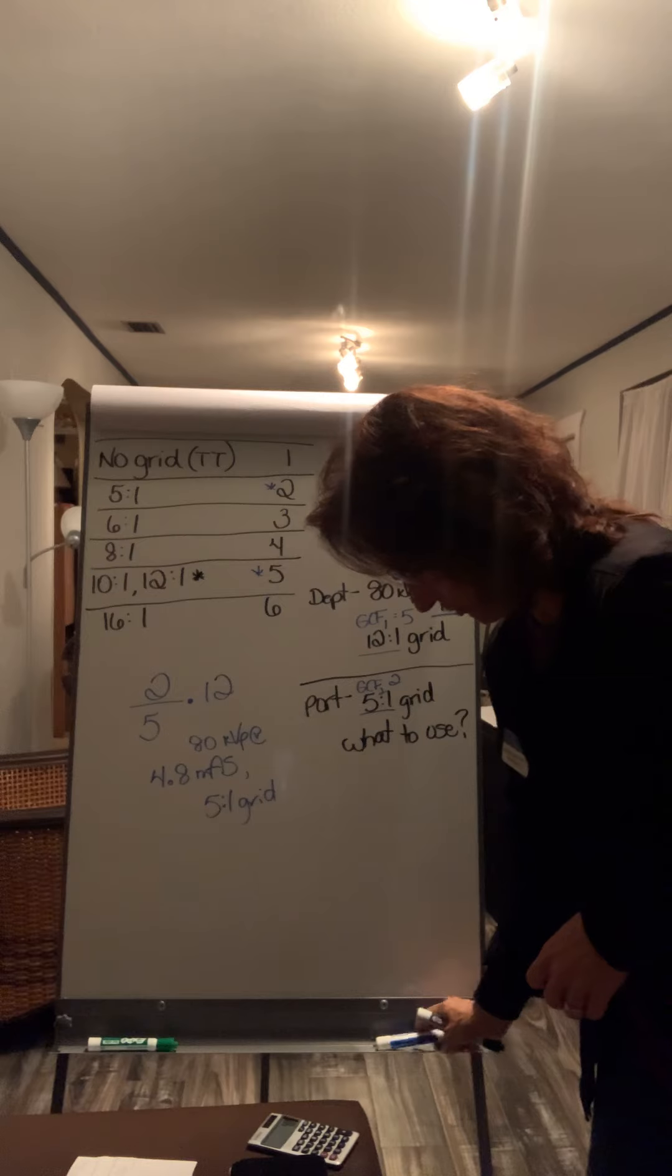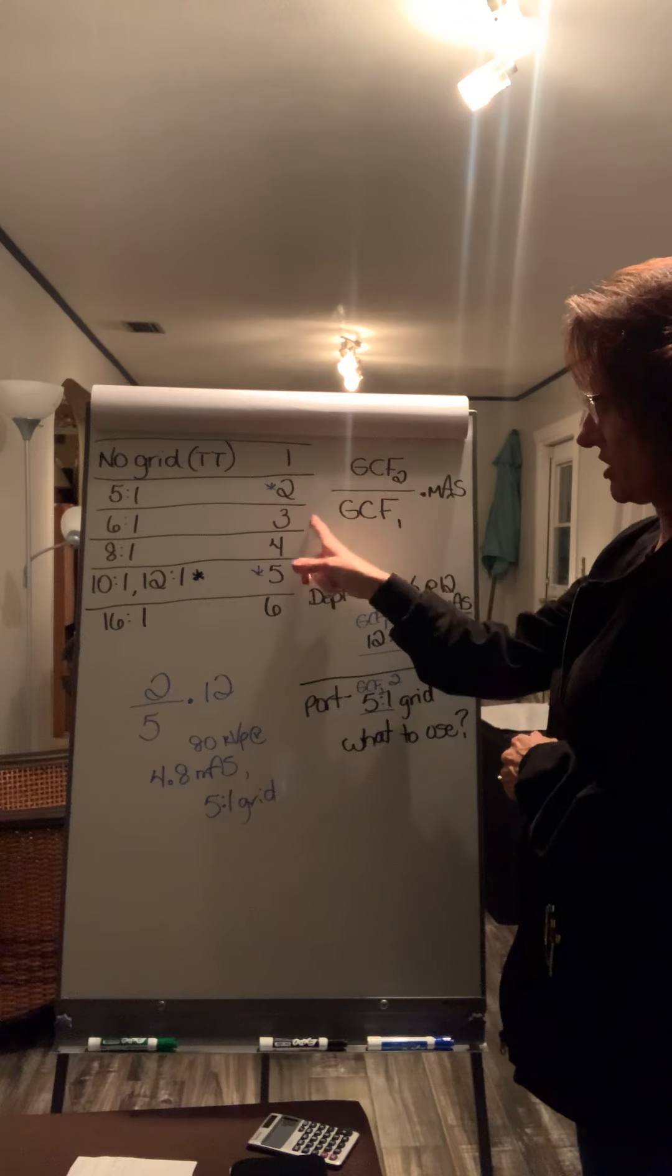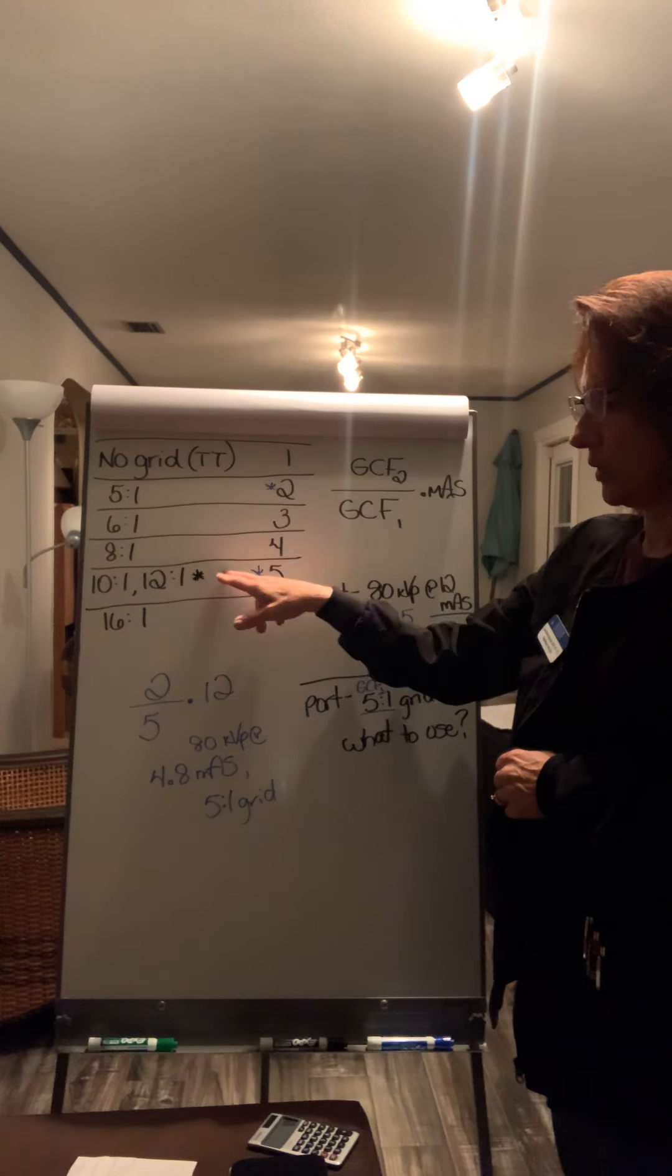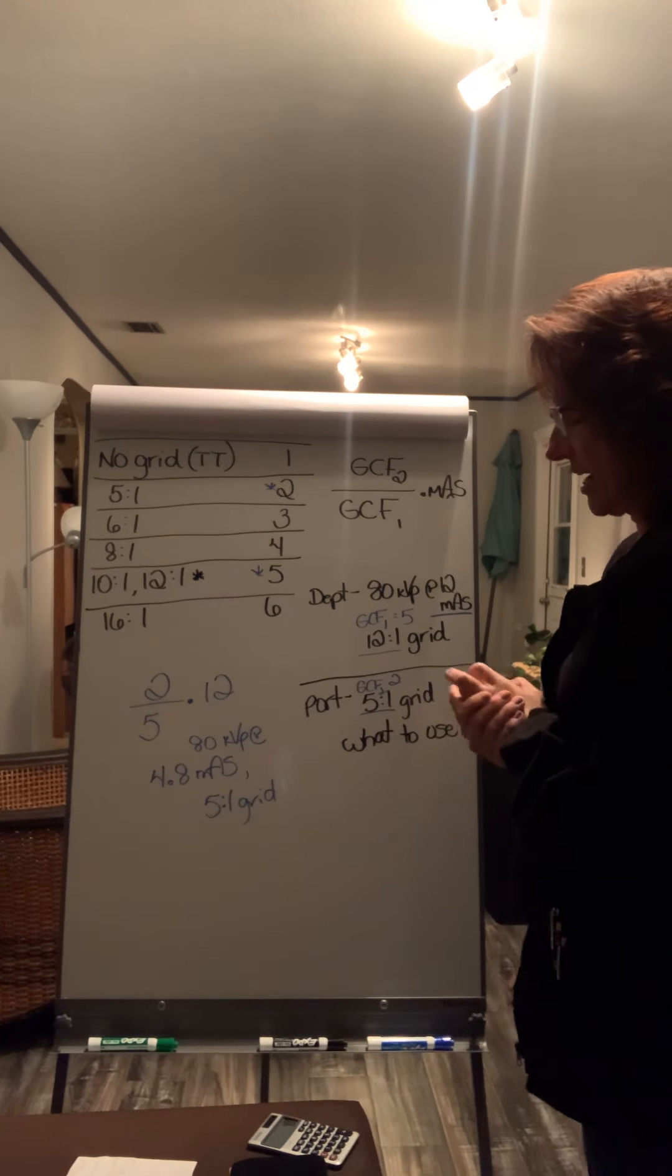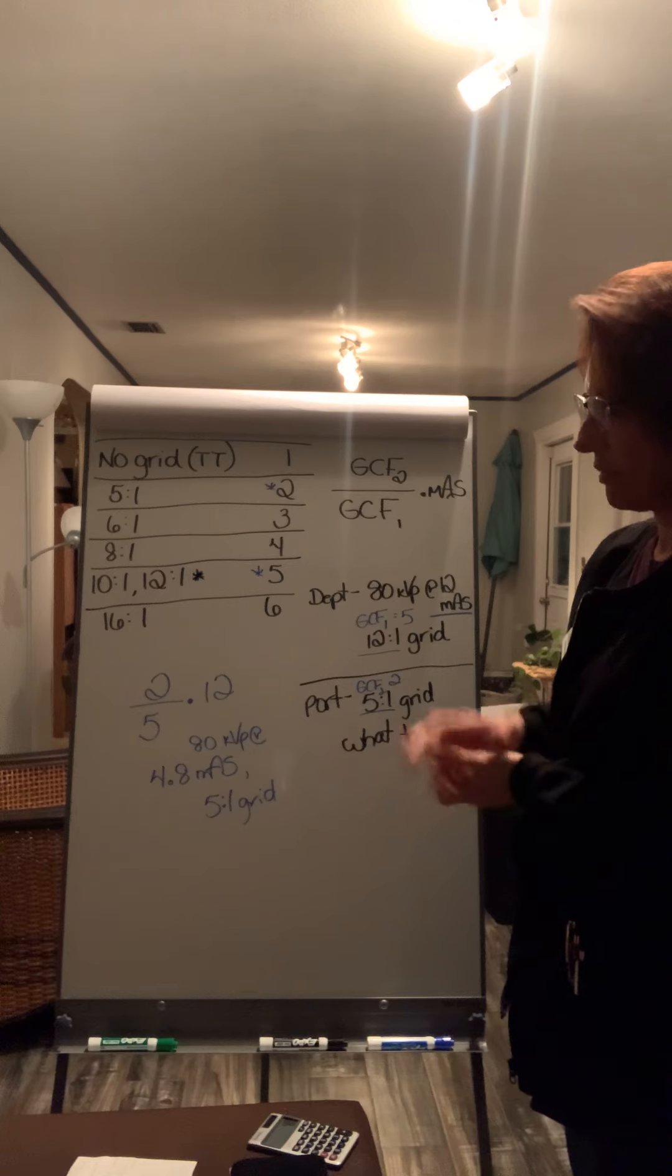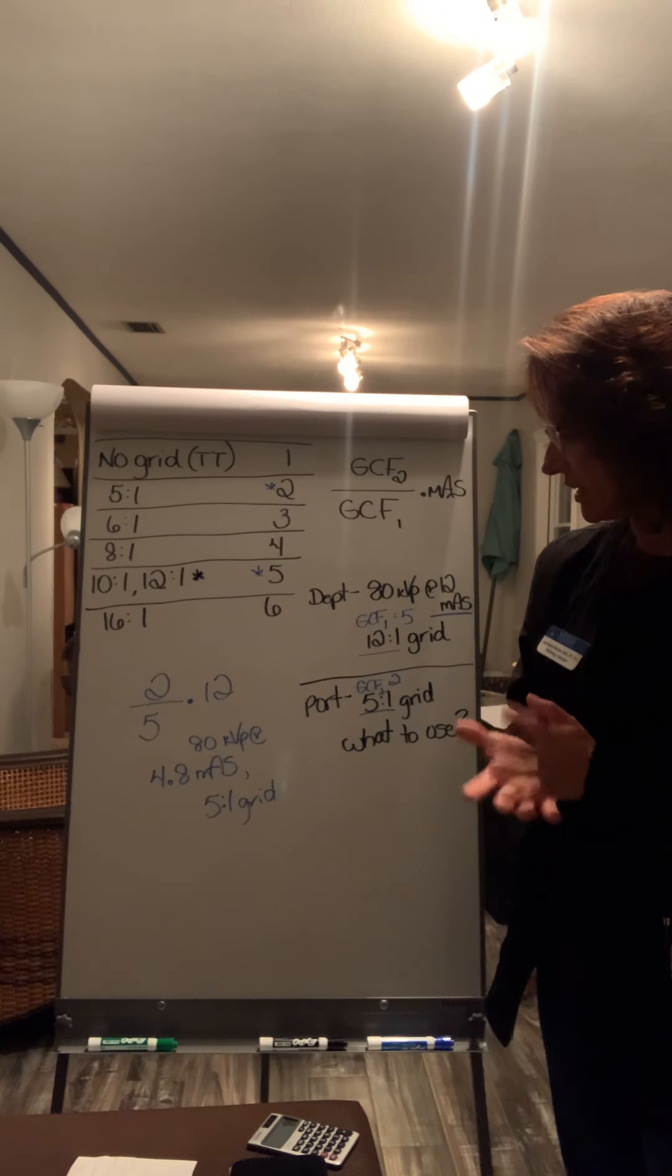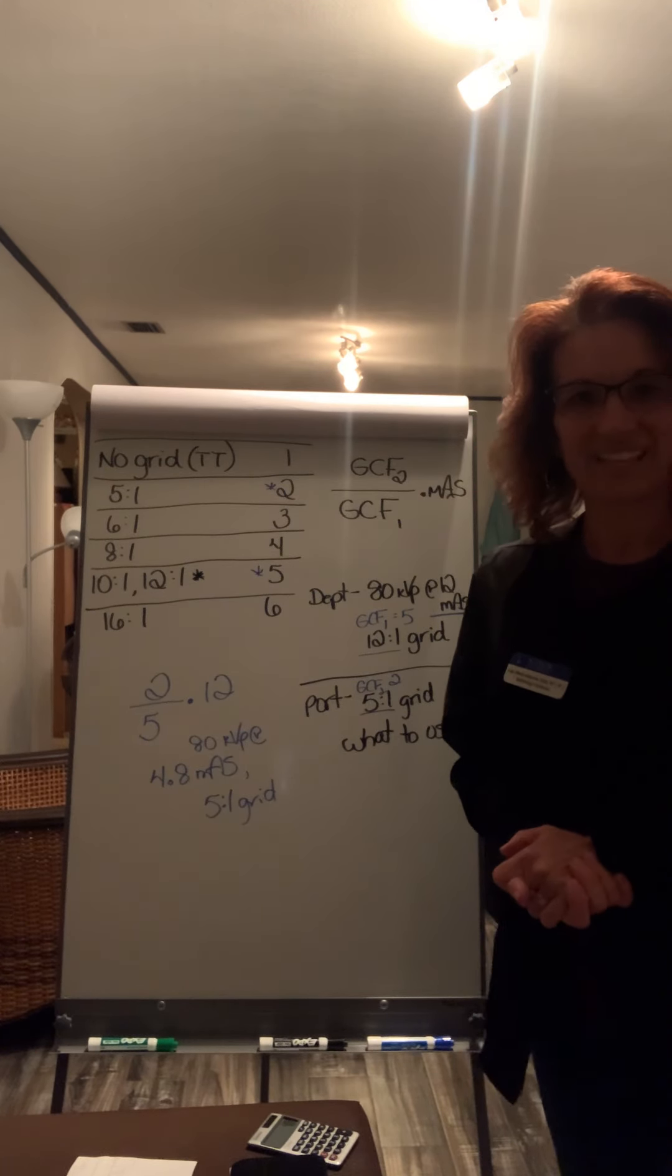And that is the grid conversion formula. Again, this stands for grid conversion factor, which is going to be one, two, three, four, five, or six. And then these are tabletop, five to one grid, six to one, eight, 10 and 12 to one, which are normally our wall buckies and our table buckies. And then a 16 to one grid is the highest grid ratio. Higher grid ratio, more lead, better at scatter cleanup, but you also have to be more precise in your positioning. Hopefully that makes the grid conversion formula make a little bit more sense. And if you have any questions or comments, I'm happy to answer those and try and clear that up. Thank you so much.